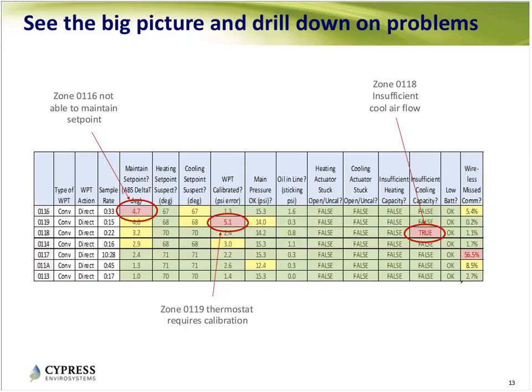So that column with the colors tells you which are the worst zones down to the medium and better ones. As you look to the right, you can see what the likely problems are: a calibration problem, a main air pressure problem, oil in the line, oscillation, a stuck open actuator, or insufficient heating or cooling. These are all very typical issues for pneumatic or general terminal units.